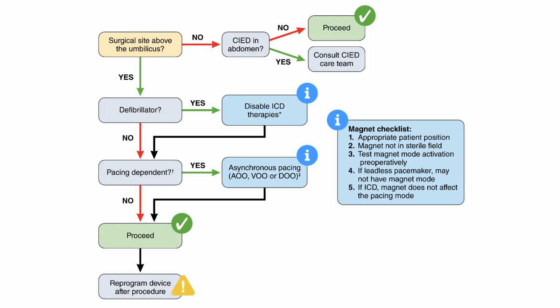If the defibrillator is there, the next step is to disable ICD therapies through the magnet if no adjustment to the pacing is required. But if pacing adjustments are required, then that should be done through programming. Next, if the patient is pacing dependent, the device should be put into an asynchronous pacing mode so that electromagnetic interference will not cause inhibition of pacing. And once those are done, proceeding with the surgery is the next step. And finally, we want to make sure that reprogramming the device after the procedure is always performed before the patient leaves and tachytherapies are re-enabled, for example.